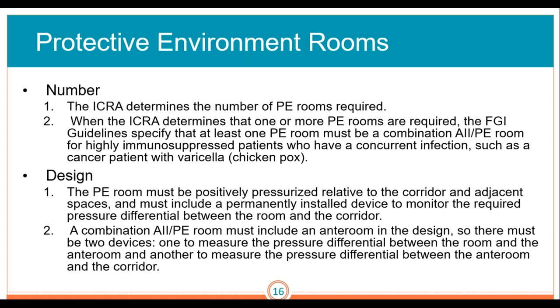Regarding protective environments: the ICRA determines the number of PE rooms required. When the ICRA determines that one or more PE rooms are required, the FGI guidelines specify that at least one protective environment room must be a combination of an AII room and protective environment room for highly immunosuppressed patients who may have a concurrent infection, such as a cancer patient with varicella. The protective environment room must be positively pressurized relative to the corridor and must include a permanently installed device to monitor the required pressure differential. A combination AII-PE room must include an ante-room, with one device measuring pressure between the room and the ante-room, and another measuring between the ante-room and the corridor.